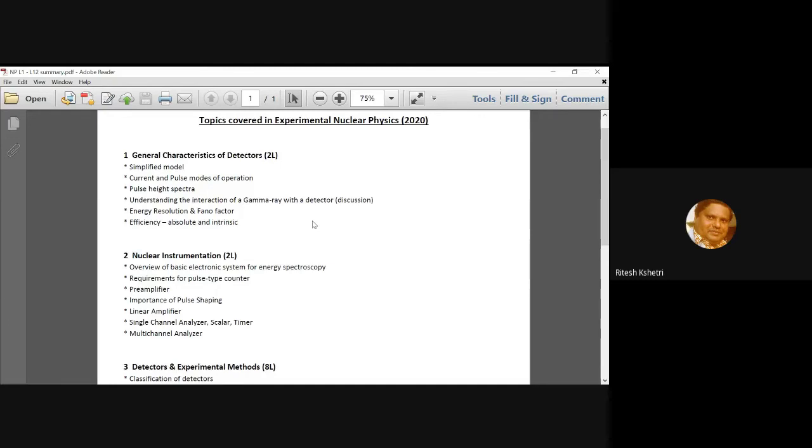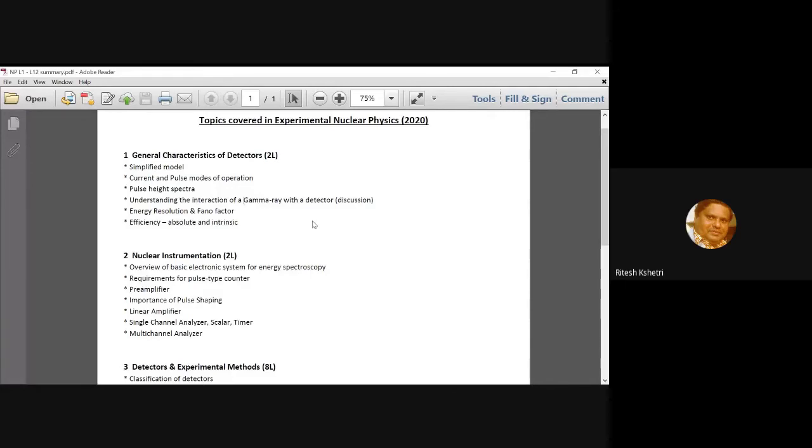What are the requirements? What do we expect from a pulse type counter? And then I talked about that just after the detector, immediately close to it lies the pre-amplifier. And what was the importance of the pre-amplifier? The impedance matching criteria and also getting rid of some of the noises. These were discussed.